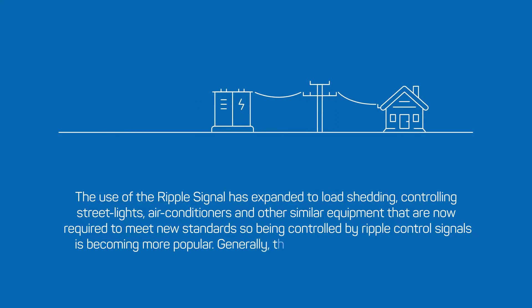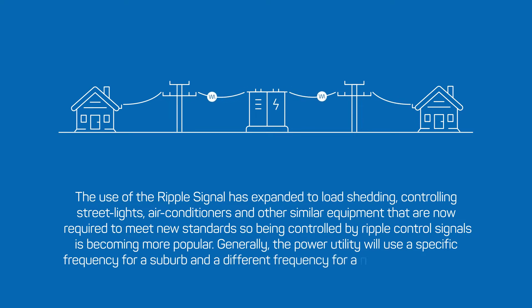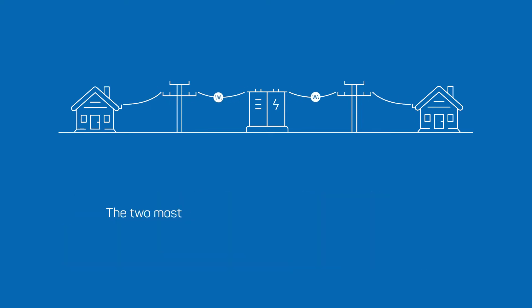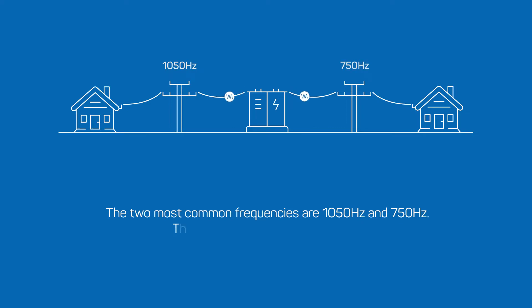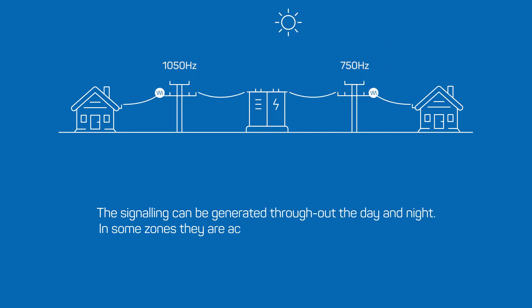Generally the power utility will use a specific frequency for a suburb and a different frequency for a neighboring suburb. The two most common frequencies are 1050 Hertz and 750 Hertz, though there are several others in use too. The signaling can be generated throughout the day and night — in some zones they are active from early morning to late night.